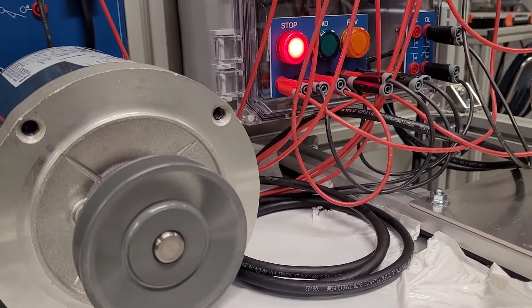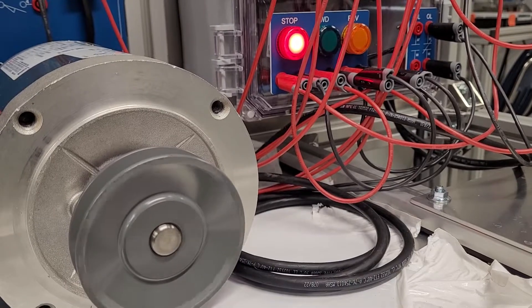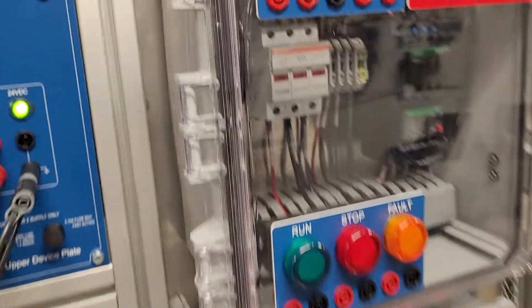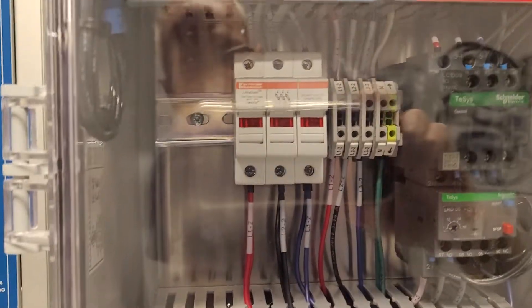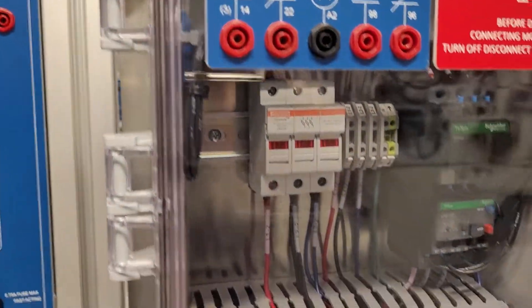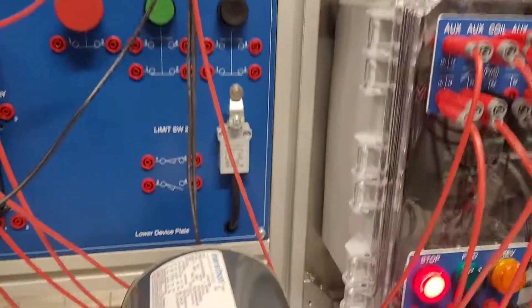Okay, so what just happened is the overload heated up. Now I've done this test over and over and I have not blown a fuse. I've had meters on here testing the inrush. It can get pretty high when you're operating it, when you're plugging it like that.